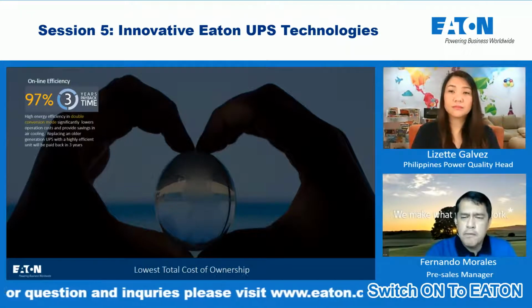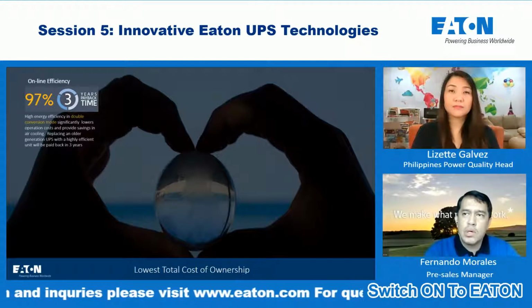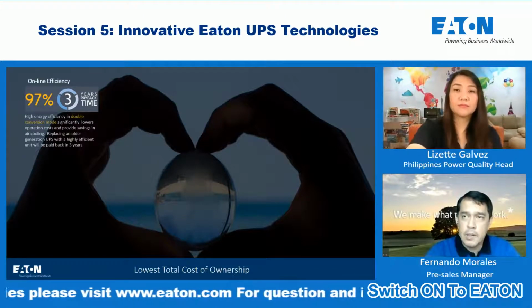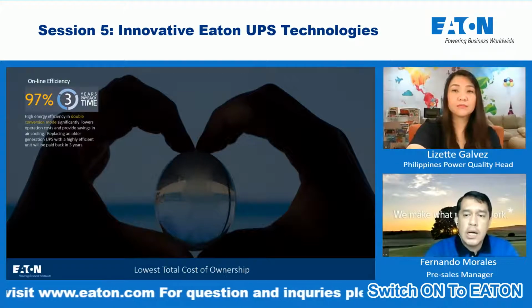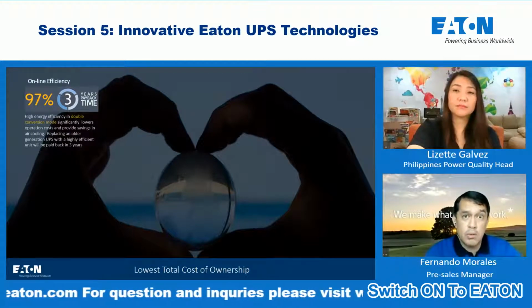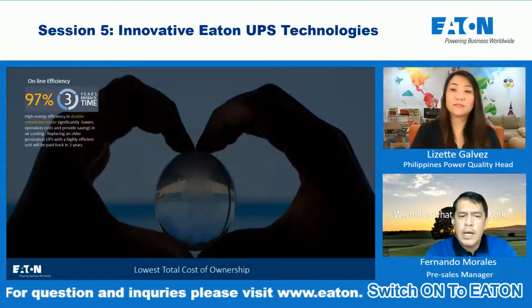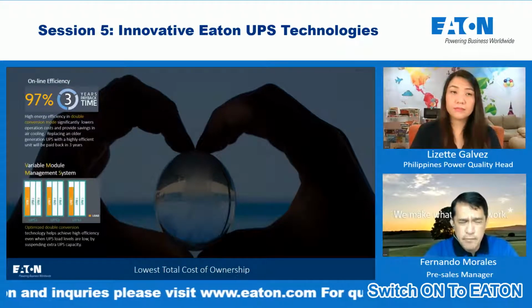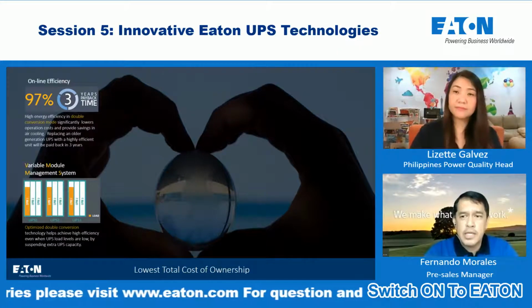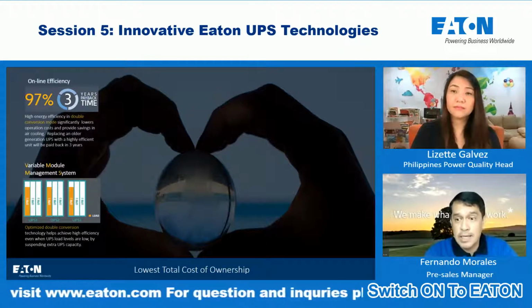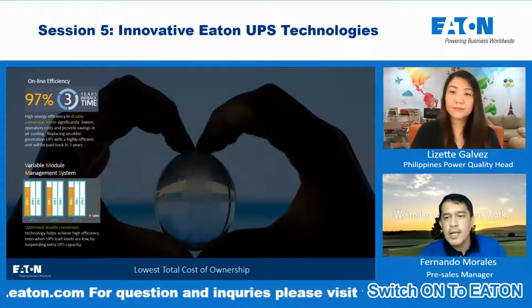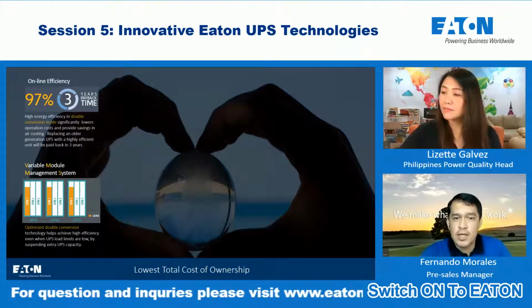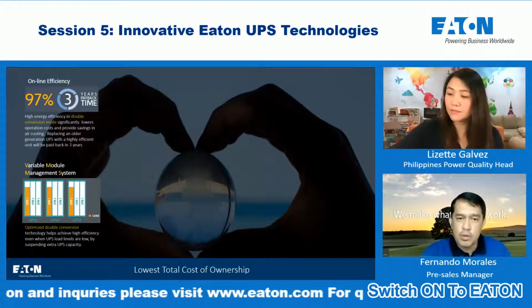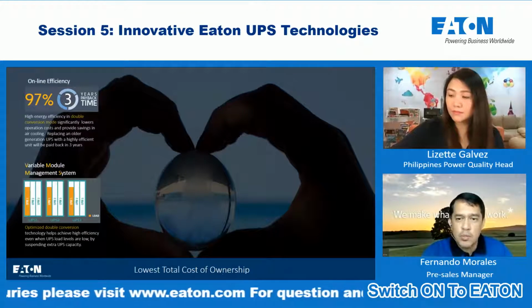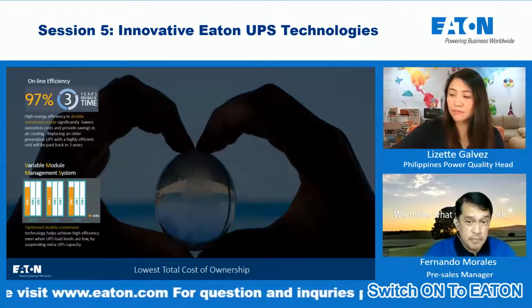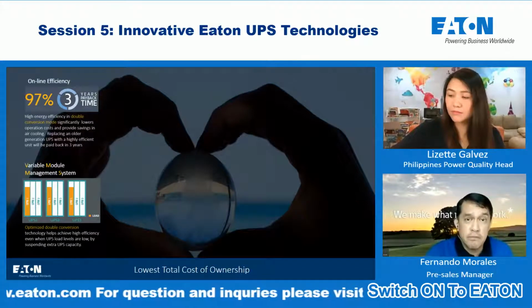But if you still want to operate the UPS in double conversion mode and your current load is very low, in our modular UPS system we incorporated a feature called the Variable Module Management System, or VMMS - sometimes called optimized double conversion technology. The UPS still operates in double conversion mode, but with this technology it helps achieve high efficiency even when the UPS loads are very low.